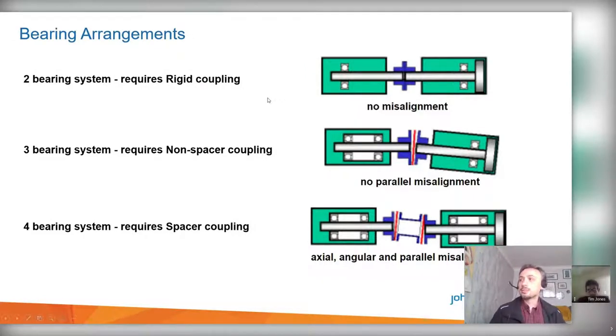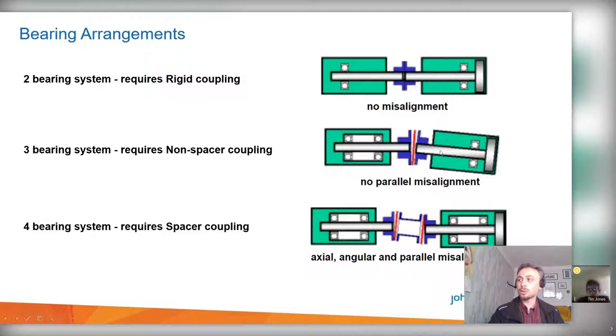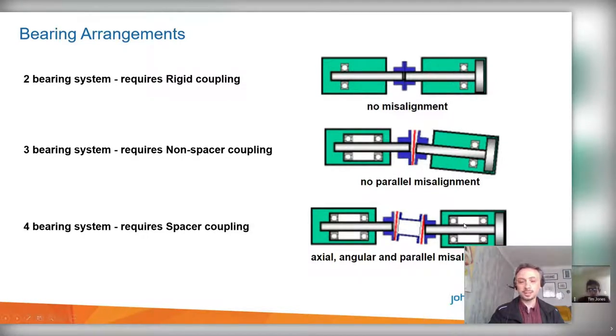Bearing arrangements determine what type of coupling is needed. With just two bearings in a system, a rigid coupling is required to prevent shafts from bending excessively. With three bearings, a single flexible element can accommodate angular misalignment but not parallel misalignment. A four-bearing system with a spacer and two flexing elements allows parallel shaft offset, and the reaction forces on the bearings are significantly lower compared to other arrangements.